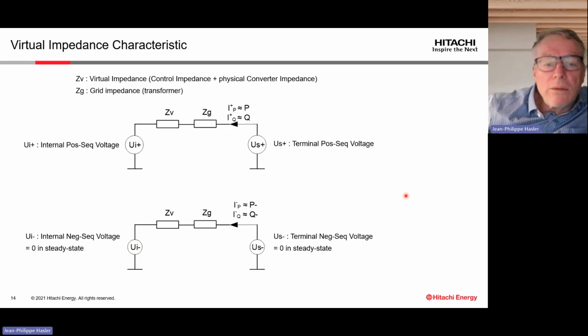So just to resume, what is the equivalent circuit of our STATCOM? Here we have the virtual impedance, sometimes called the control impedance, plus the physical impedance of the converter. And we have the transformer, and all these are constant. This definition of control impedance, I think, is taken from the German TSO. And this control impedance has to include a resistive part. That is for the positive sequence.